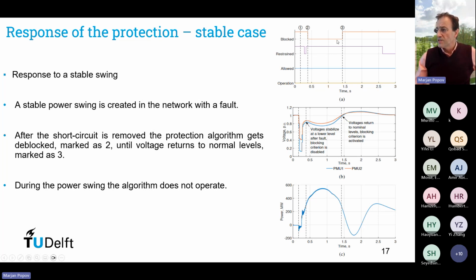The protection is blocked until instant three, where we actually see here that the voltage is recovered. It exceeds above one per unit, and then the protection is deblocked. However, at the same time, we have a stable case, and that is why the protection is kept restrained. So there is no operation because we have a stable power swing.